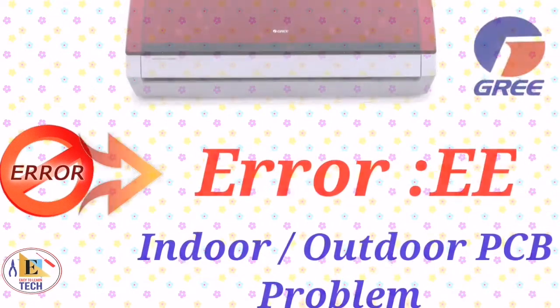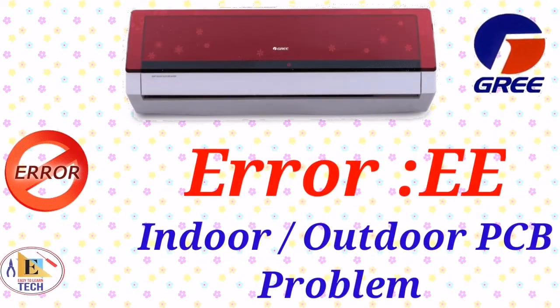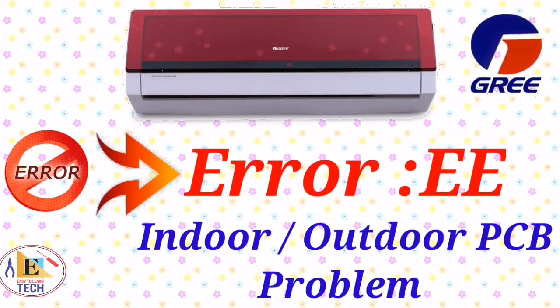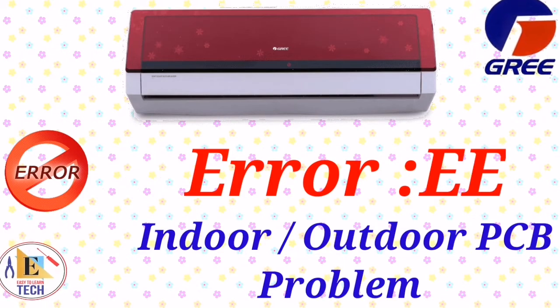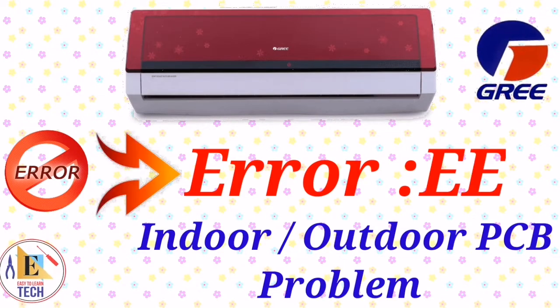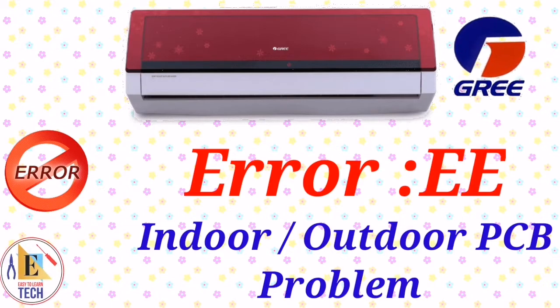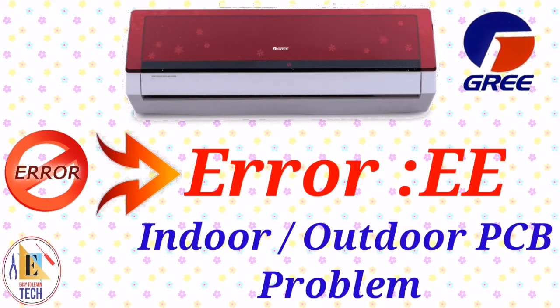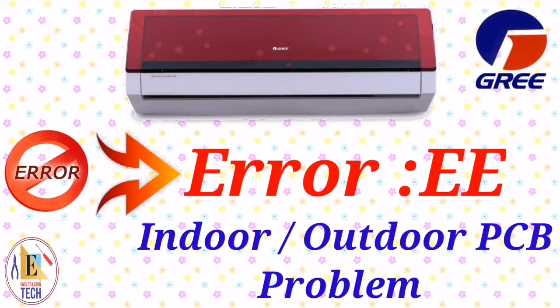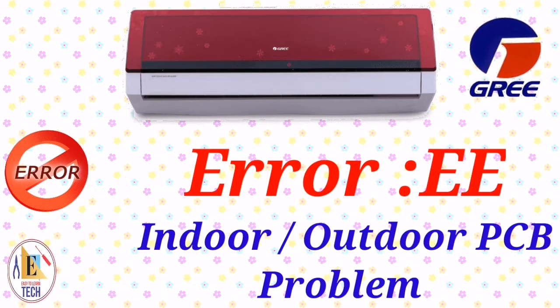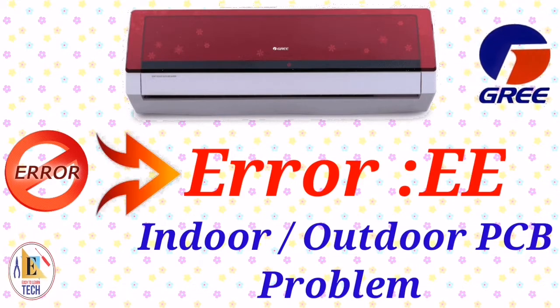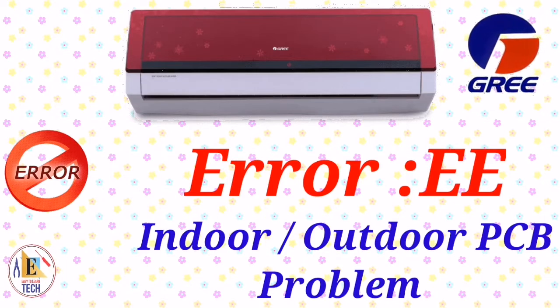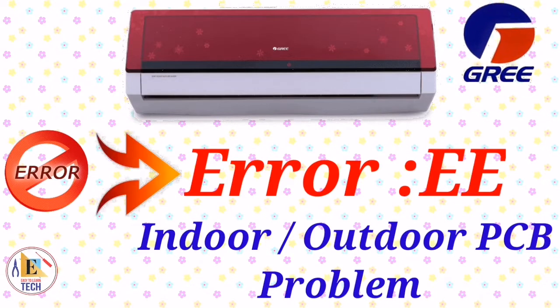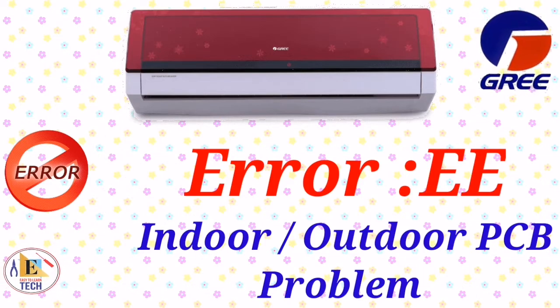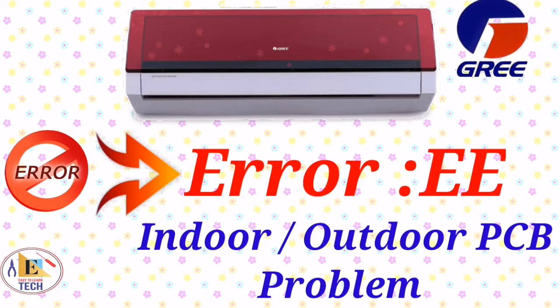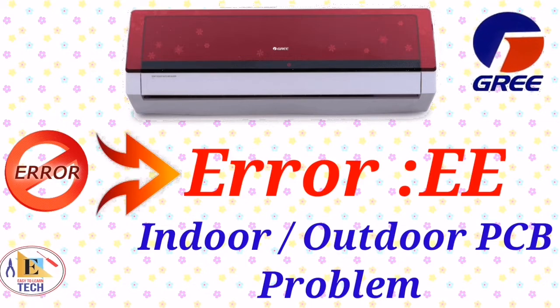Let's see the next error code. When you see EE in your display, it means indoor or outdoor PCB problem. First, you have to check the indoor PCB, if the output supply from the indoor PCB is okay or not. If the output supply from our indoor PCB is not coming perfectly, it means our indoor PCB has a problem. If the output supply from our indoor PCB is coming perfectly, then you have to check the outdoor PCB, the power supply going to the compressor and the return communication. If it is not perfect, it means our outdoor PCB is faulty. Then you need to change the outdoor PCB, and our unit will be in working condition.